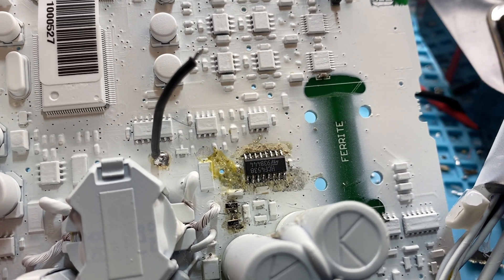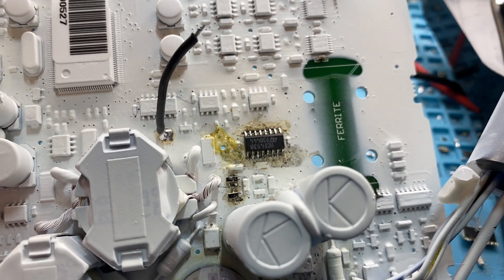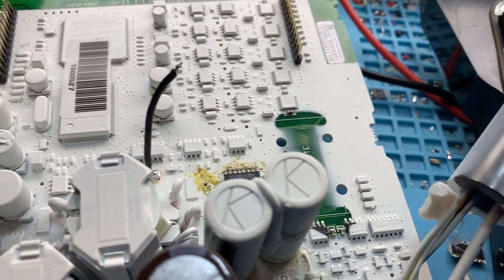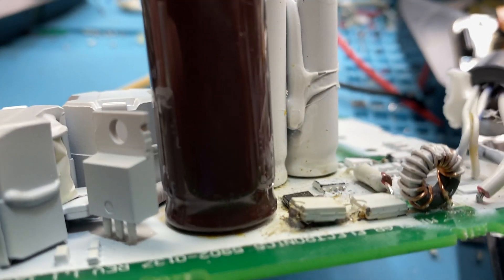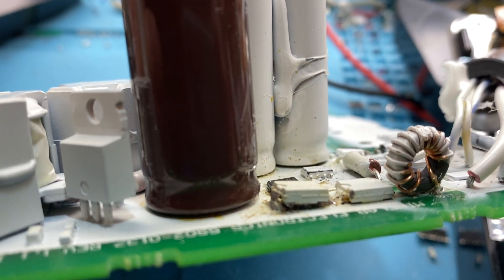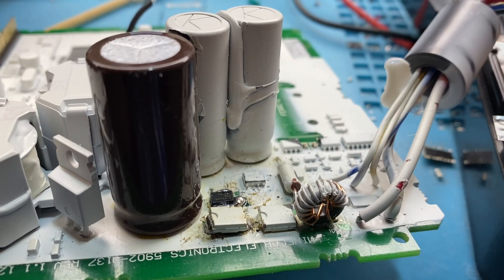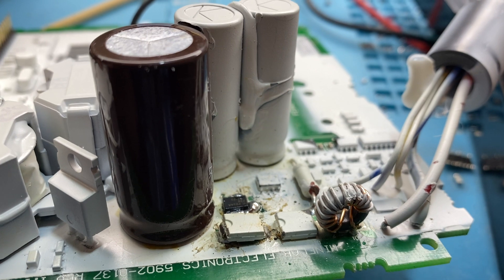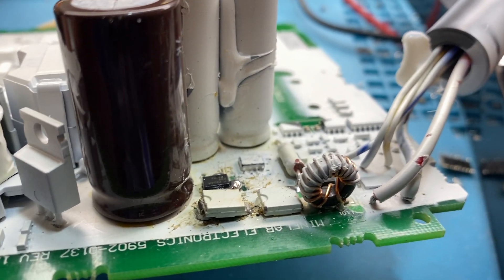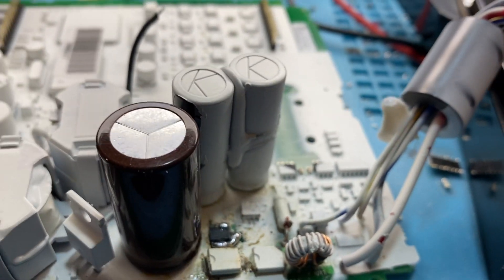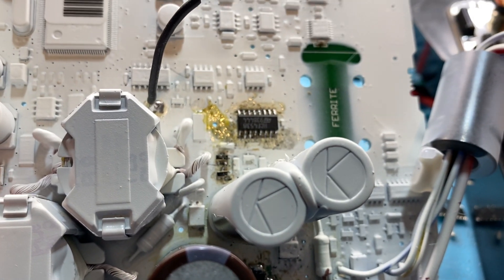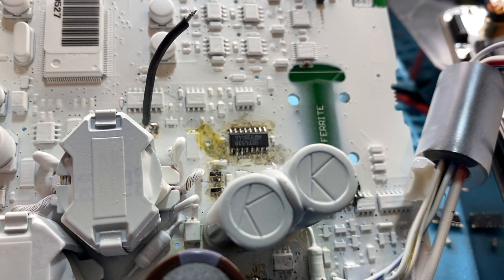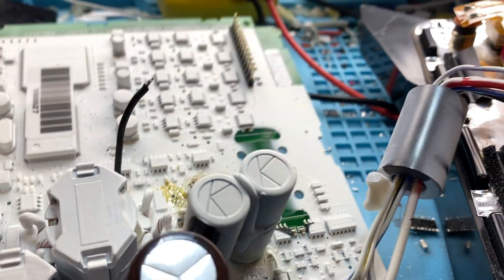There's a lot of those used in the GP 3000s. Those things are full of those 4538s. The rest of it's okay. I had to lift the diodes off there. I had funny continuity and it just looked like leakage, so I lifted those. I had to check everything, but it wasn't. It was going back in past those, through those transistors there, and then the ADG333 was shorted.